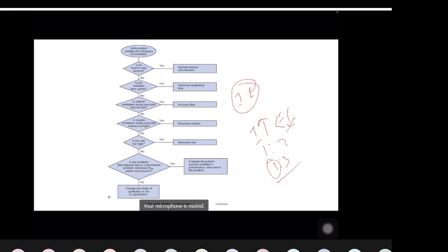occurs especially when the backup respiratory rate has been set to a very minimal value. Usually in a volume control mode, we often set the respiratory rate at 15 or 16, so the chance of an apnea alarm is much lesser here. It's particularly seen in pressure support ventilation or SIMV mode, where the SIMV rate has been reduced to a low value, where the patient triggered breath is very minimal.